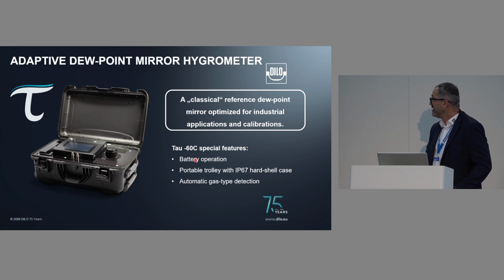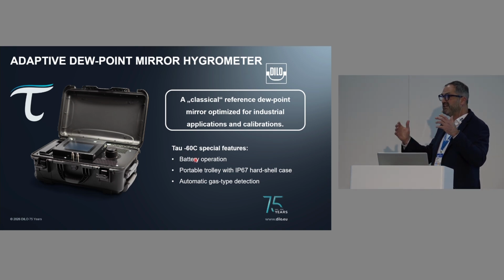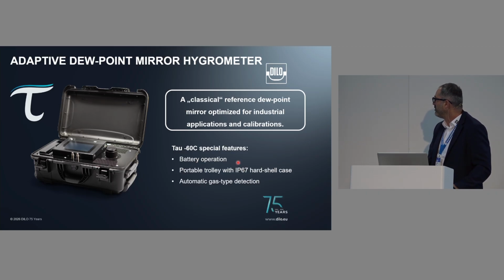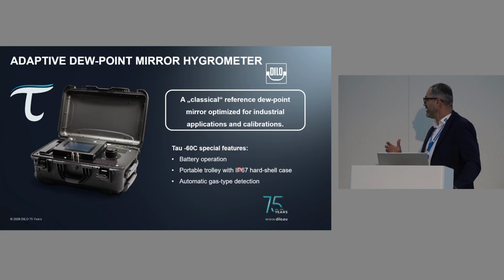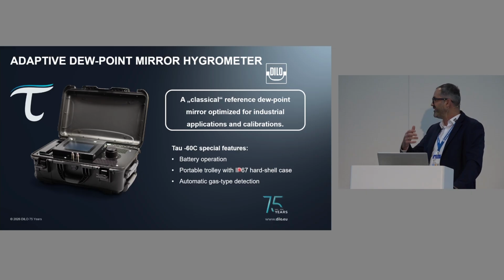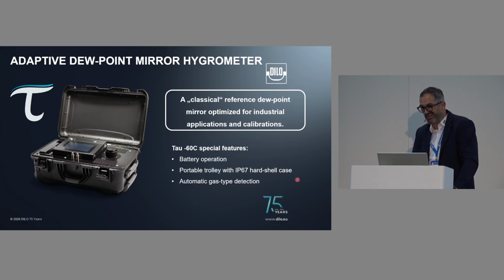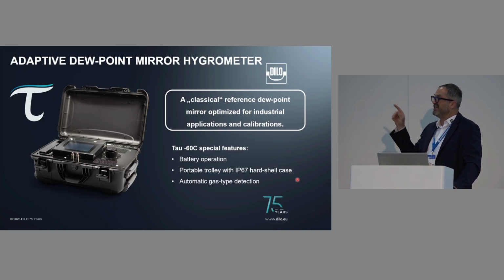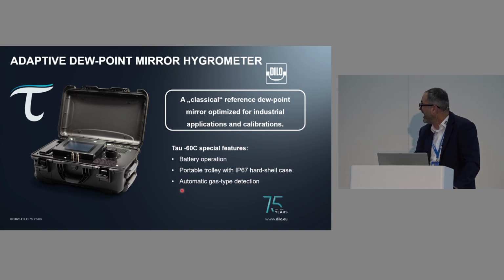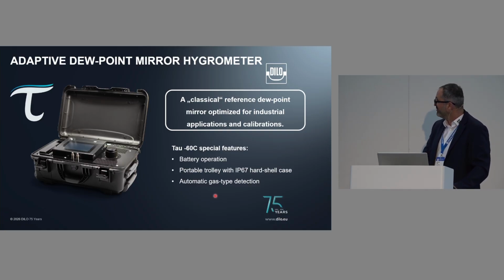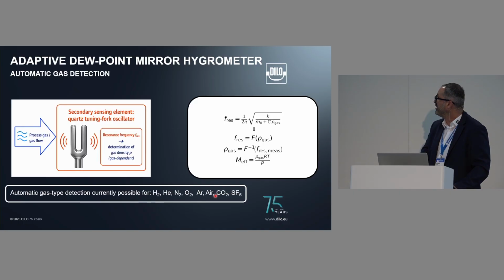It means it facilitates the measurement or the calibration on site. So it has a battery operation, and it comes in a portable trolley that is to a certain degree water protected and dust protected. So you can also use it in robust environments, let's say. And now the point is, why is it adaptive? The clue here is that it has an automatic gas type detection. And this is what makes it adaptive. And I will explain it in more detail on the next slide.